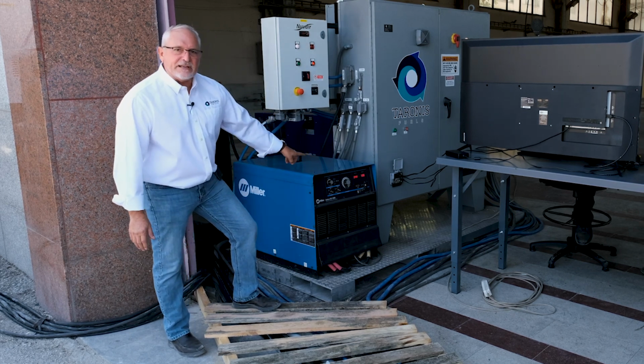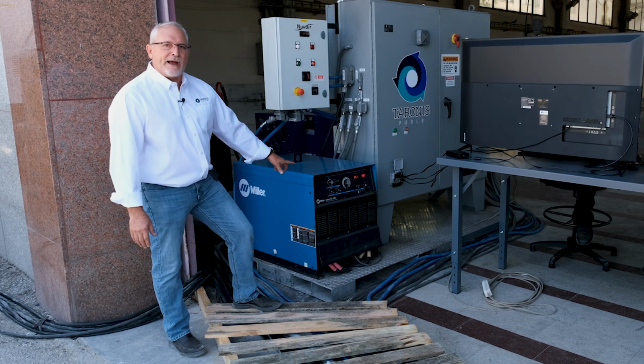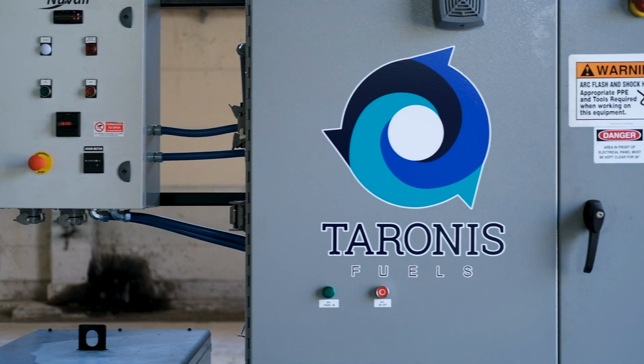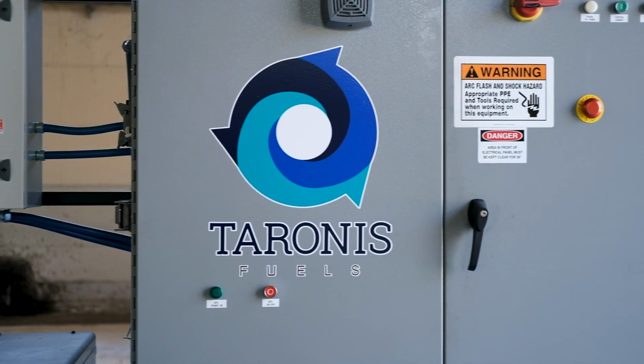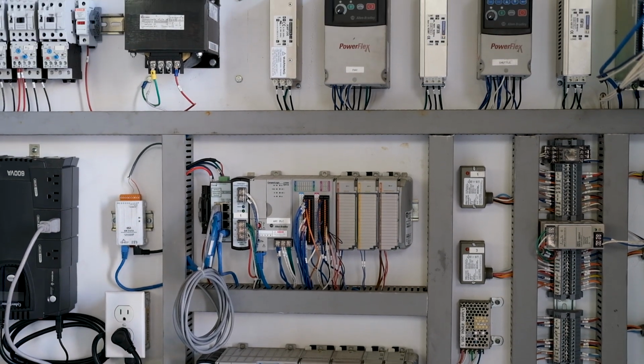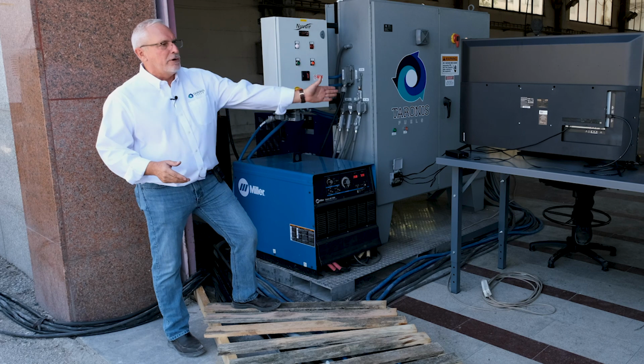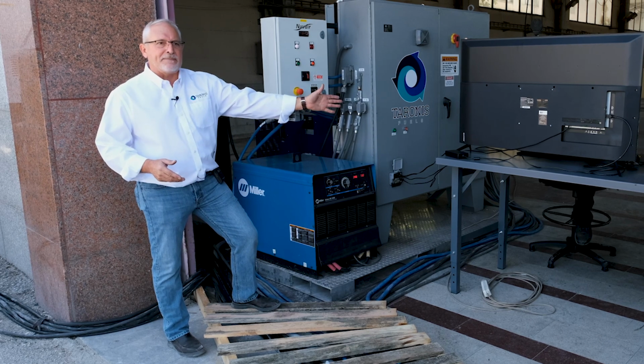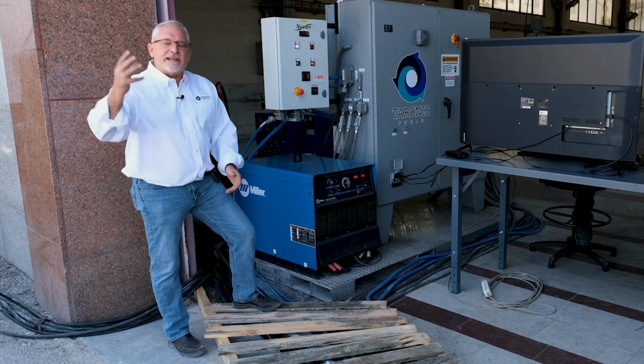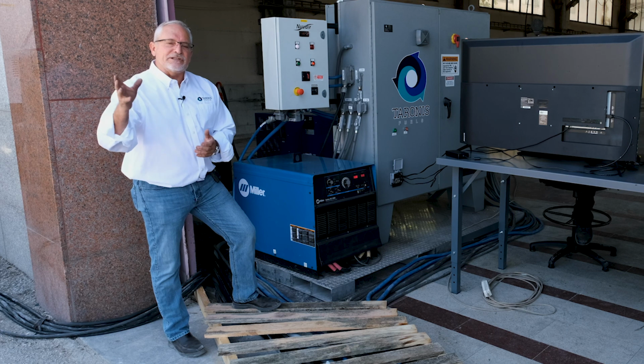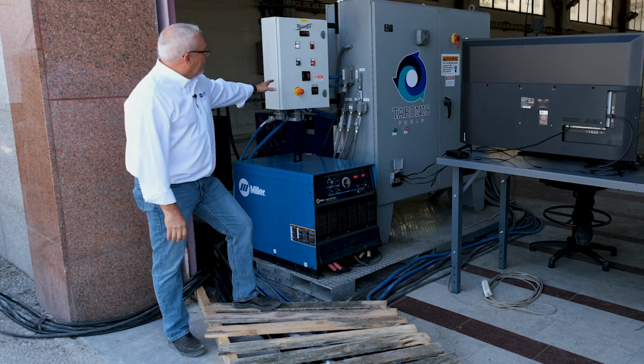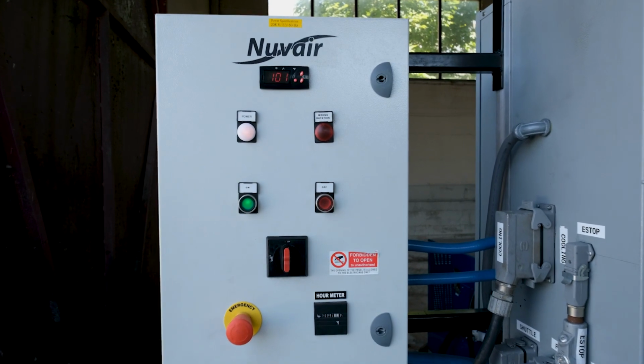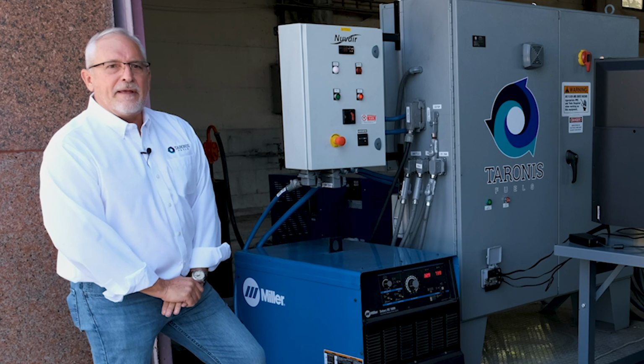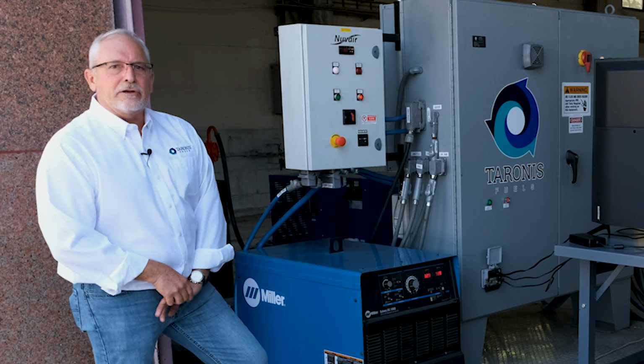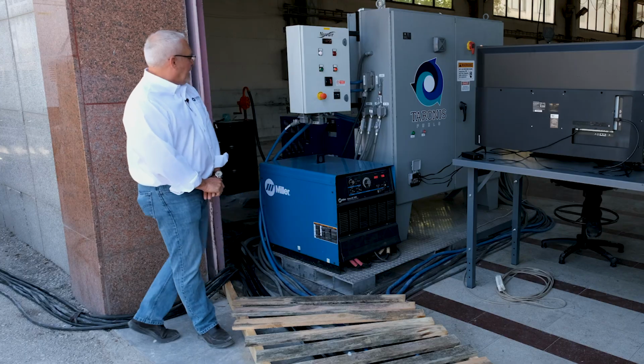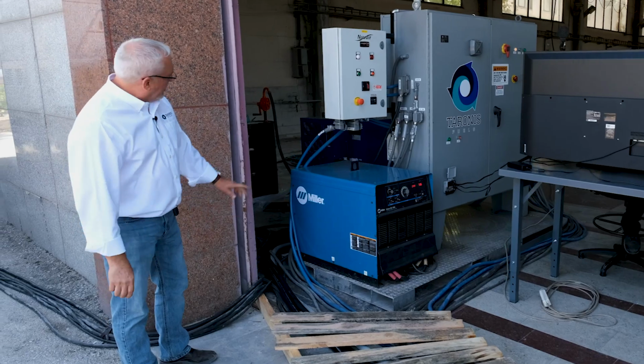And on there you can basically see the voltage and the current that is currently being supplied to our plasma arc. This box that you see to the far right is actually our control box. In there we have two PLCs. One PLC basically talks to the man-machine interface here that is on a laptop computer, and the other PLC basically takes all the input and controls from the system and controls the arc. And then one last item here on this skid is our compressor controller, and that basically is the control capabilities for our compressor.